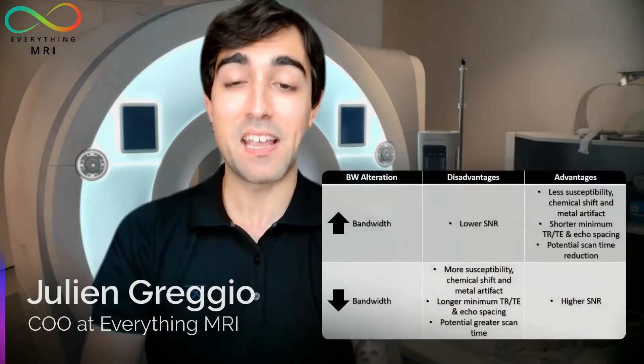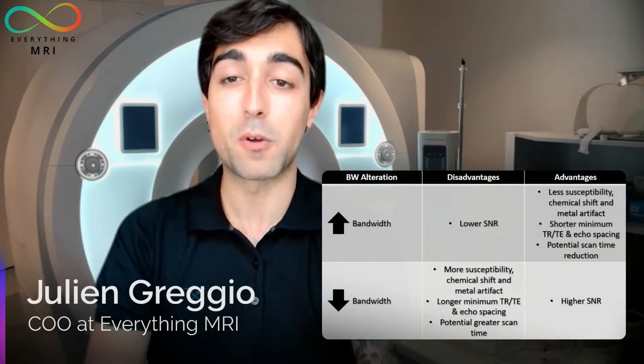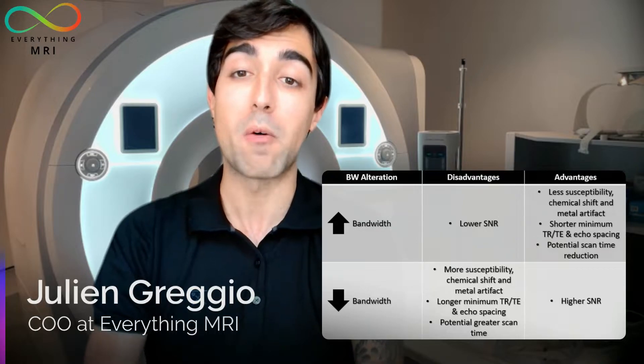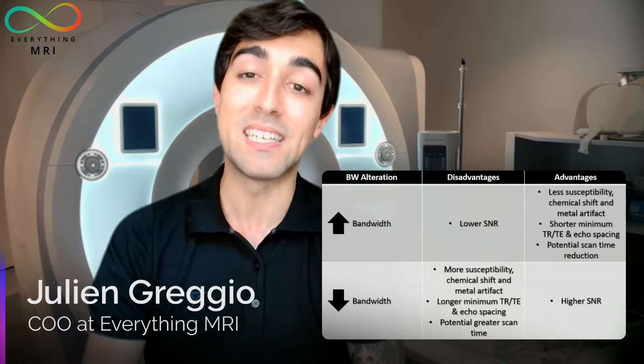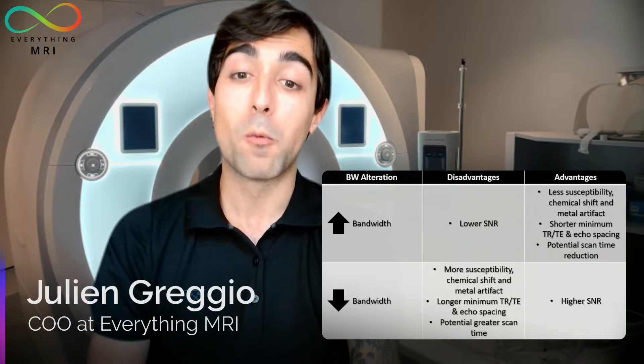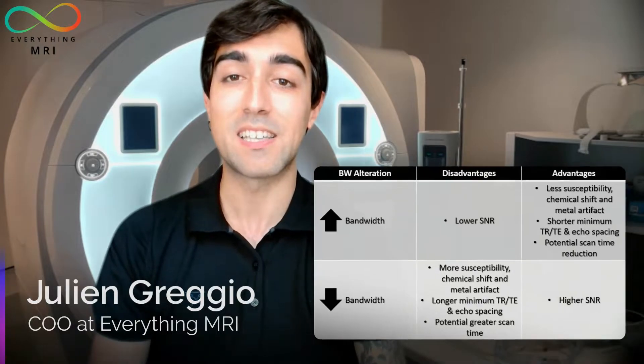With this table we want to summarize what could be a potential consequence on our image quality of either increasing or decreasing the received bandwidth. When we decide to boost the received bandwidth, we also increase the highest frequency sampled in the echo. Translated onto our image, this means we will sample a greater component of noise and the overall signal-to-noise ratio will therefore be reduced.